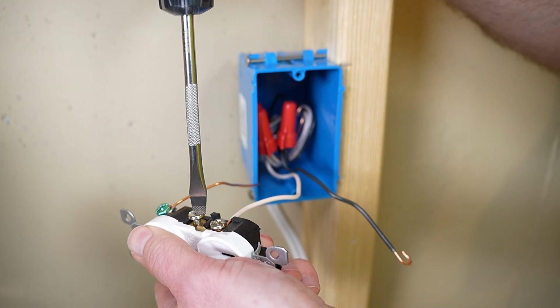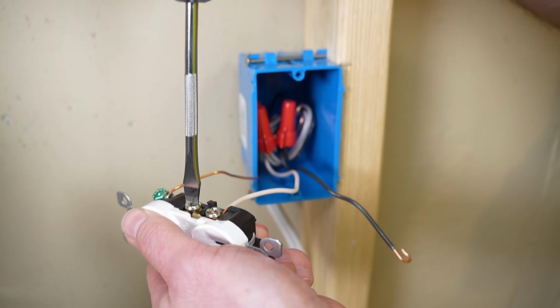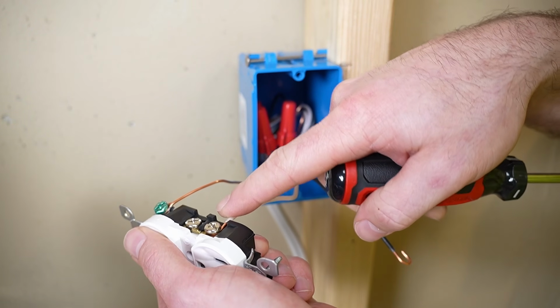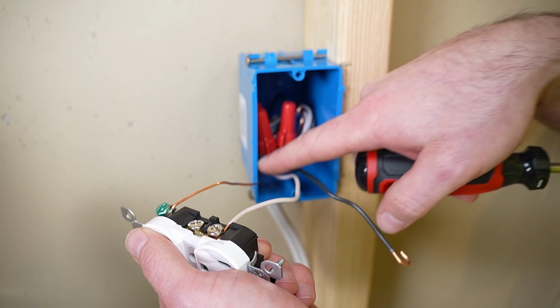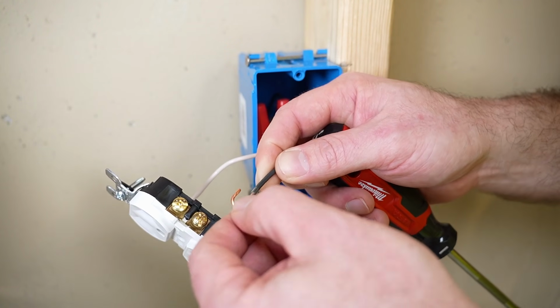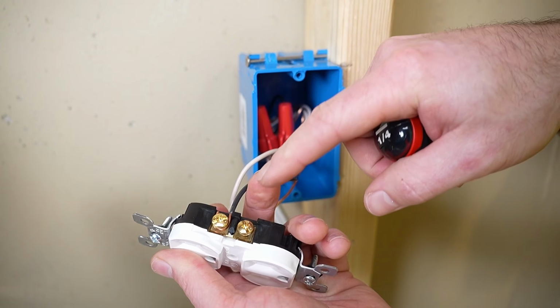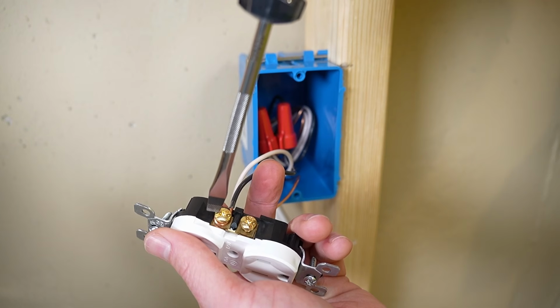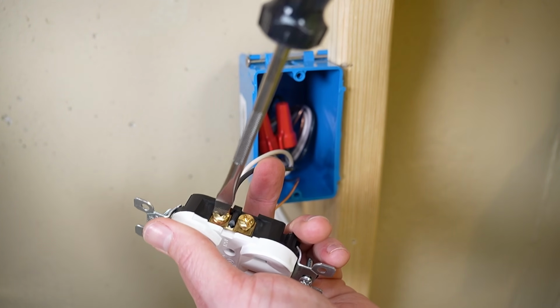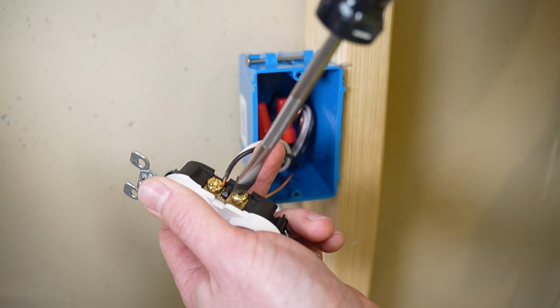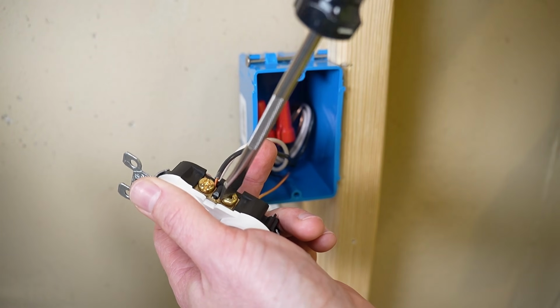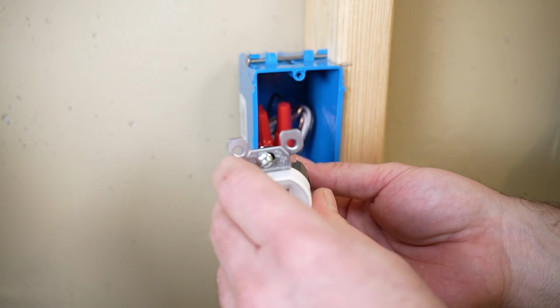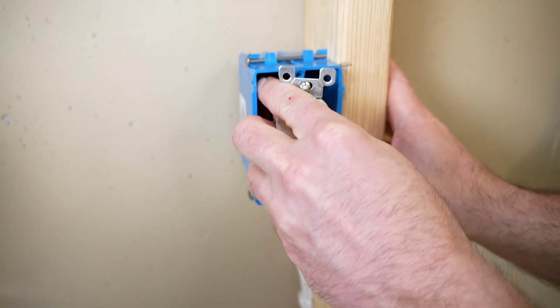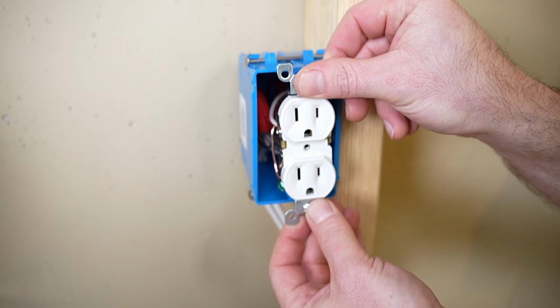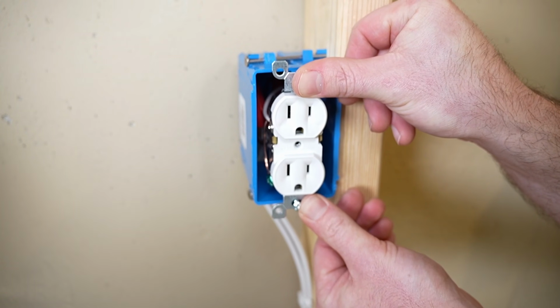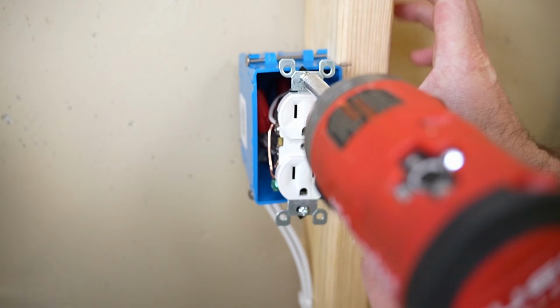It is also a good habit to tighten down the unused screws on the receptacle. It lessens the chance of one of the wires touching this bare ground wire in the box. Lastly, we can install the hot wire on the gold colored terminals. Again, same thing, we wanna make sure that wire is looping the same direction that the screw is tightening. And we'll go ahead and tighten up that extra screw as well, just so it's not hanging out there. And there we go, this receptacle is terminated. So we're gonna push our wires back into the box, and we can start tightening these screws down and install the receptacle within the box. I'm gonna cheat and use a drill.